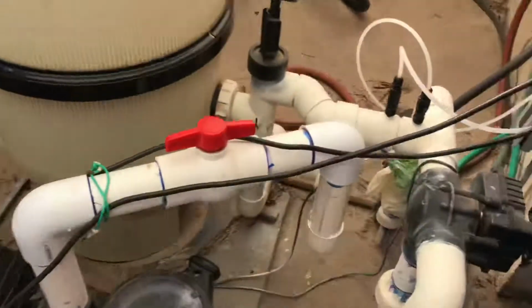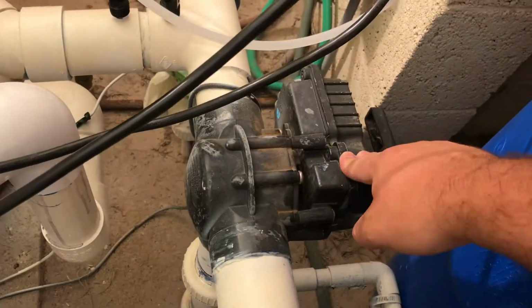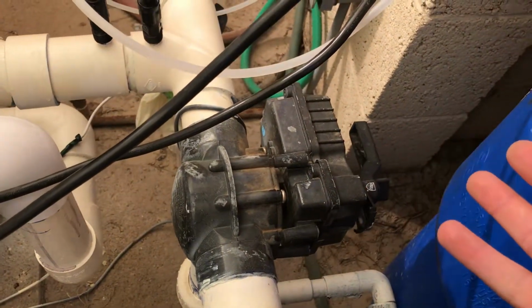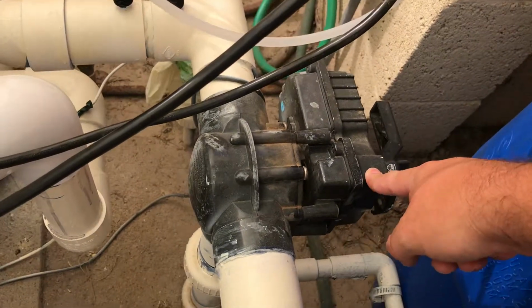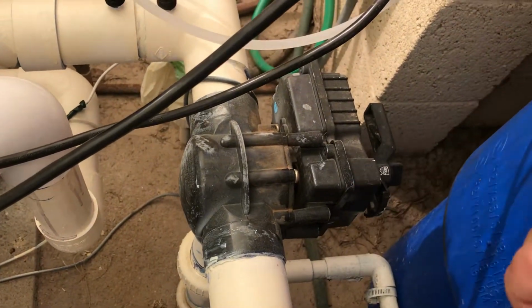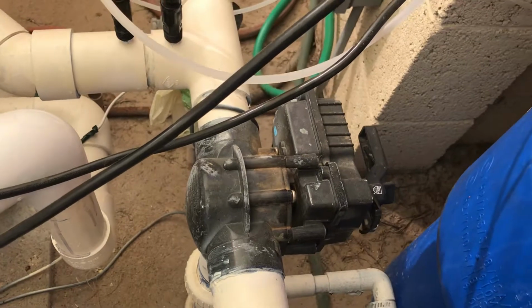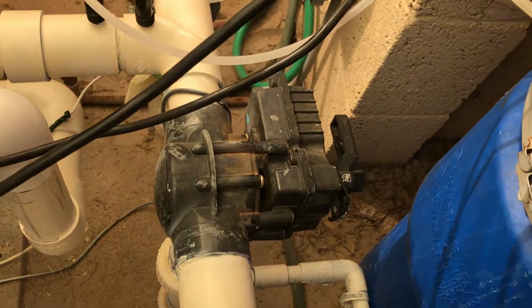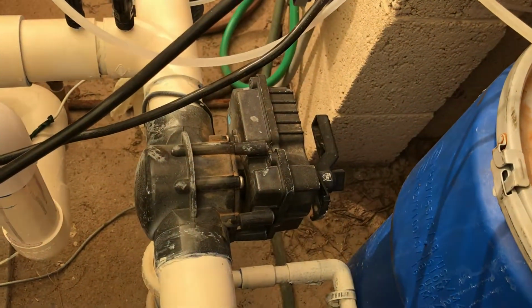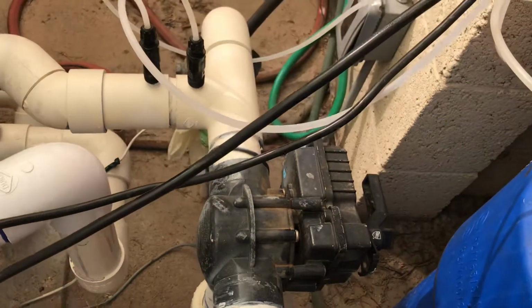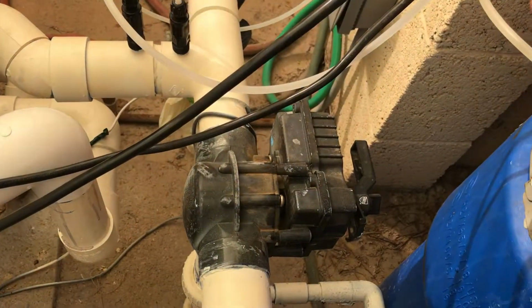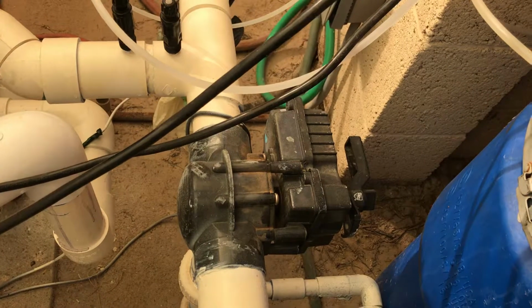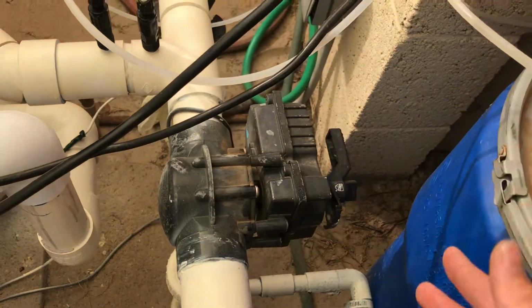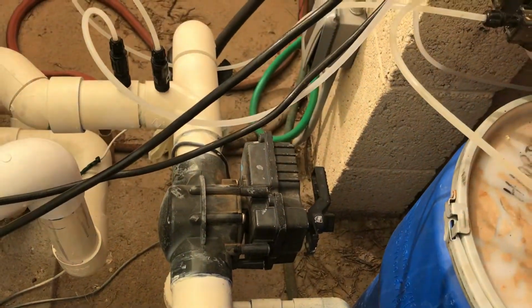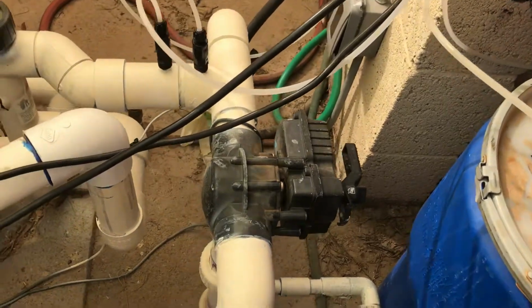As far as the relays, 3 do the speed, 2 do this Jandy valve. The reason I have 2 is so I can do 3 positions on the valve, since there's a stop limit switch on each side. You could get away with 1 relay for 2 positions, but I wanted 3 different positions, so 1 relay goes one direction, 1 relay goes the other, and otherwise it's stopped - I use timing to achieve that 3rd position.